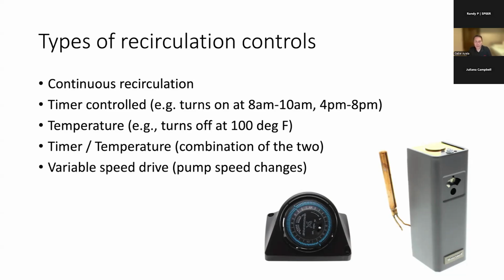Then you have some new types of controls that have hit the market recently. You might see some variable speed drive, which basically modulates the speed of the pump based on when people are using or not using hot water. But really, it doesn't turn the pump off at all. It just keeps the pump running at different speeds. It's more of a strategy to reduce the electricity consumption of the pump, but doesn't really do much in the way of reducing the distribution heat losses.